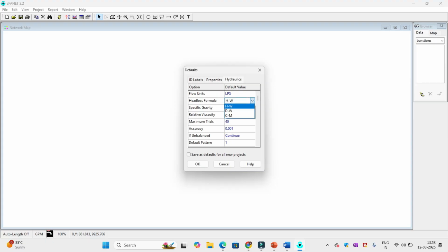In general, what is recommended is DW, that is Darcy-Weisbach. The Darcy-Weisbach equation was derived from the basic laws, using fundamental fluid dynamics. So it is not empirical, and it takes in not just pipes, but also the effects you get from wall effects. If you're adding a pump or a valve or a T, those kinds of effects are also taken into account in Darcy-Weisbach.